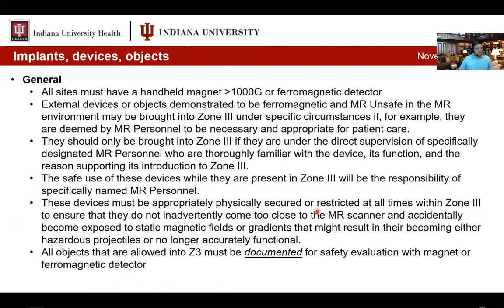General topics and implants, devices, objects. All sites must have a handheld magnet greater than 1,000 Gauss or a ferromagnetic detector. A non-ferromagnetic detector, such as the black wands that we all have, does not meet this requirement. You must have a magnet greater than 1,000 Gauss or a ferromagnetic detector. If you're listening to this right now and don't have one of these at your site, please let your administrator know this is something that needs to be changed immediately because you're not in compliance with the ACR requirements.